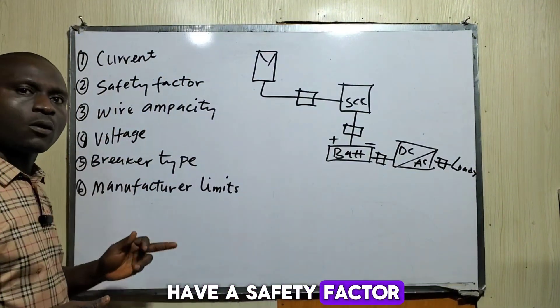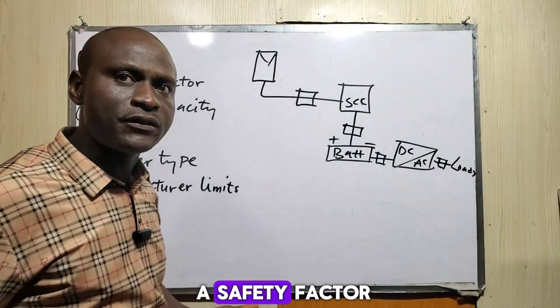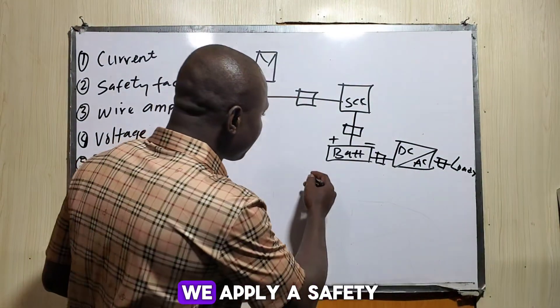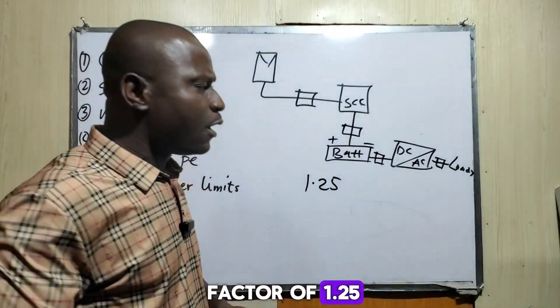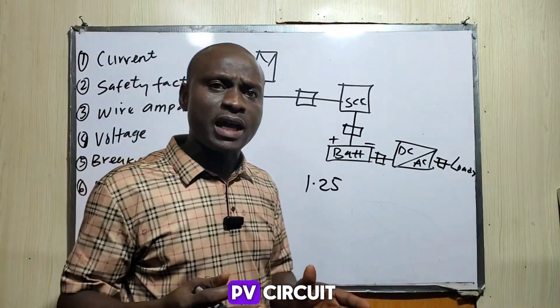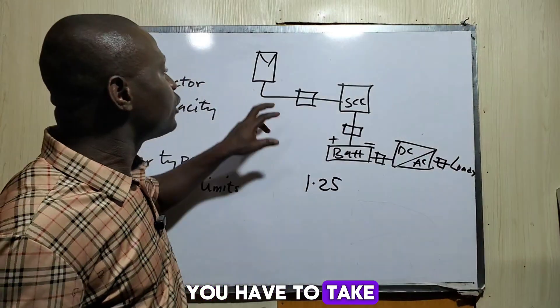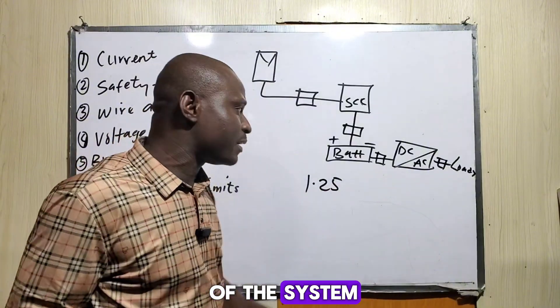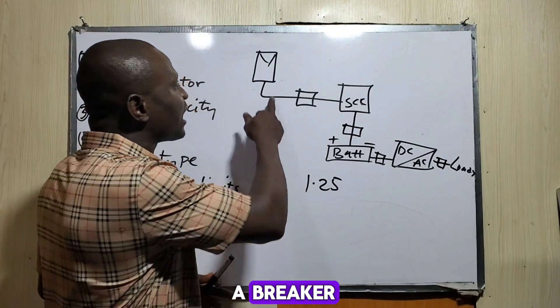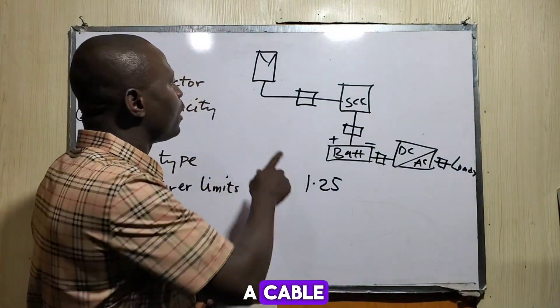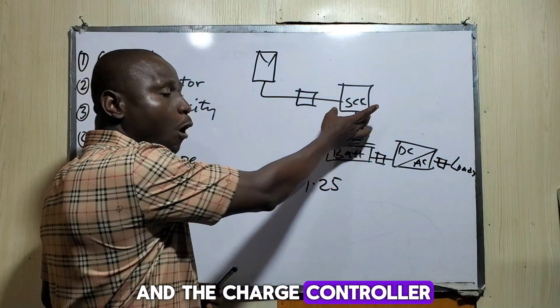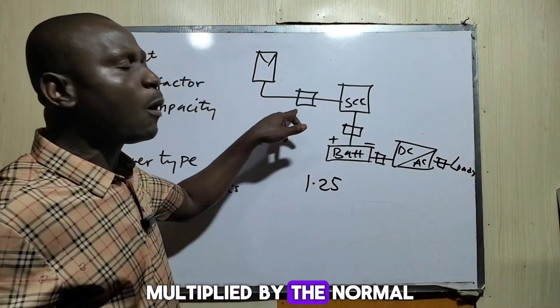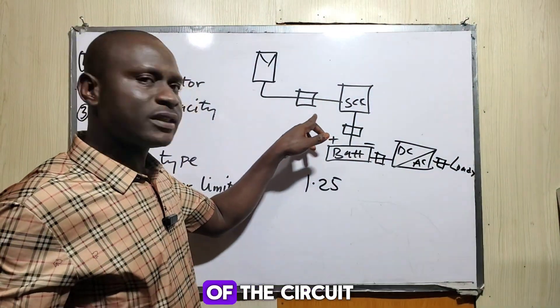Number two, we have a safety factor. We need to apply a safety factor. When choosing a breaker or a cable, we apply a safety factor of 1.25. But when sizing a PV system, you have to take into consideration the PV source side and the inverter side. When sizing a breaker, fuse, or cable between the solar panel and the charge controller or hybrid inverter, you take 1.25 multiplied by the normal operating current of the circuit.